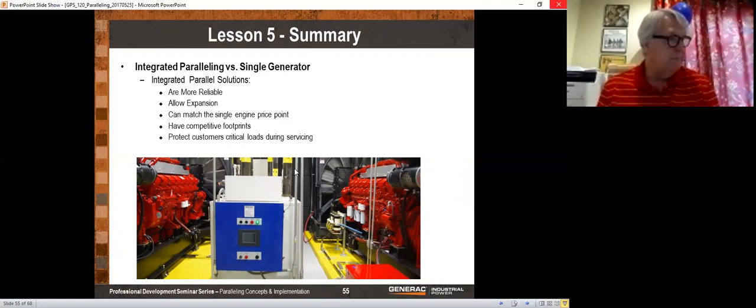All right. Is it possible to perform peak shaving with generators set up for paralleling? Is it possible? Yes. Is it practical? Typically not. Let me give you an example that we have. We test motors. We have a motor rewind shop, and when we test a big motor, it takes a lot of power, and therefore it's going to set a peak for the month that would cost us a lot of money.